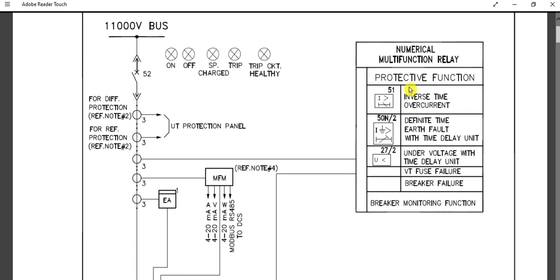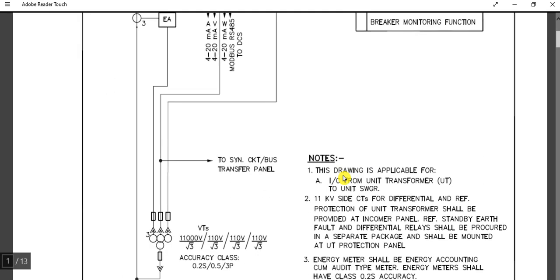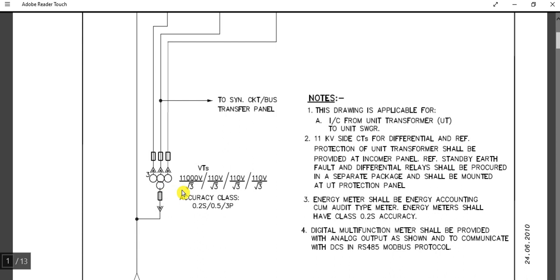This numerical multi-function relay receives current signal from the current transformer, and also requires VT (voltage transformer) or PT input for voltage measurement. So one input is the current signal from the CT, and another is the voltage signal from the VT. This VT has one primary side winding and three secondary side windings.